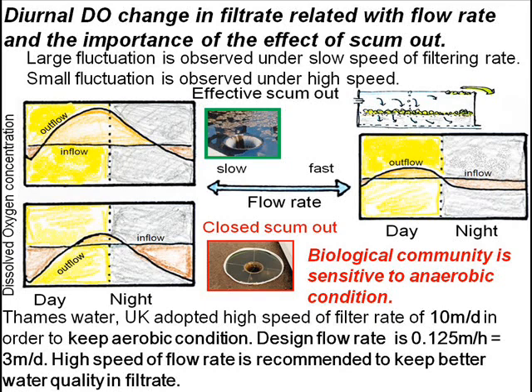The biological community is sensitive to anaerobic conditions. Thames Water adopts a high speed filtering rate of 10 m per day in order to keep aerobic conditions. The design flow of this plant is 3 m per day. Water temperature and solar radiation in Samoa are higher than in the UK, so a high flow rate is recommended.